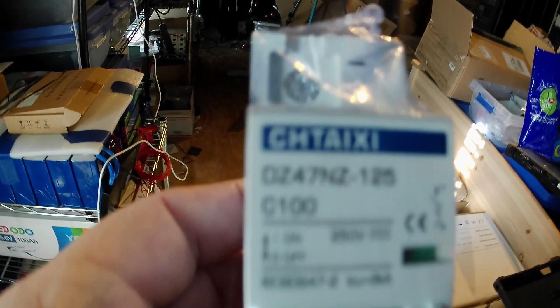It protected the cable and the battery, so I decided to go a different route. Rather than using that fuse, I got a DC rated circuit breaker right here, 100 amp, rated for up to 250 volts. Remember, DC breakers are different than AC breakers.